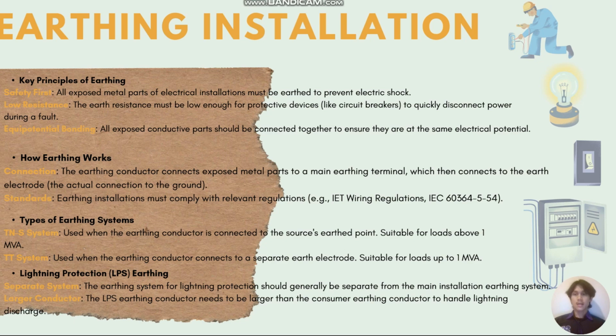And the last, lightning protection, LPS earthing. We have two points below that, which are separate system and larger conductor. First, the earthing system for lightning protection should generally be separate from the main installation earthing system. And the larger conductor: the LPS earthing conductor needs to be larger than the consumer earthing conductor to handle lightning discharge.